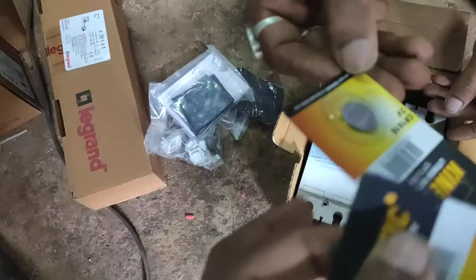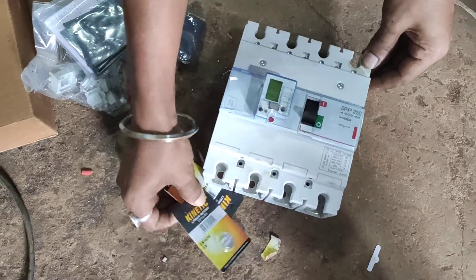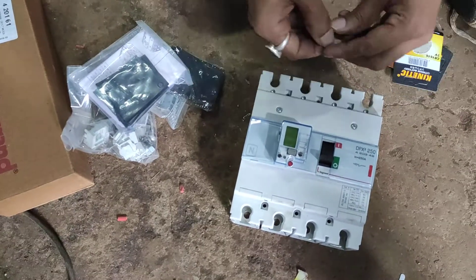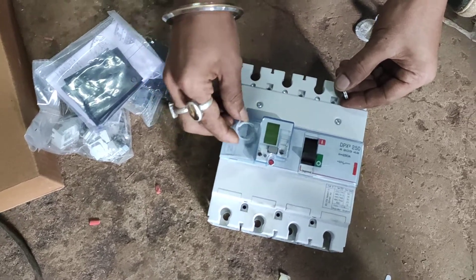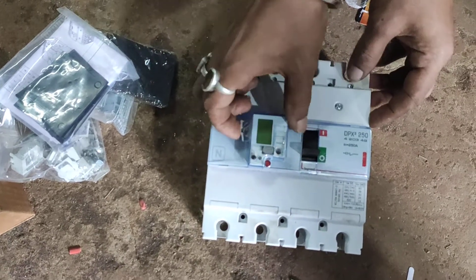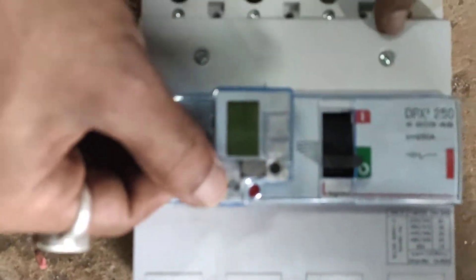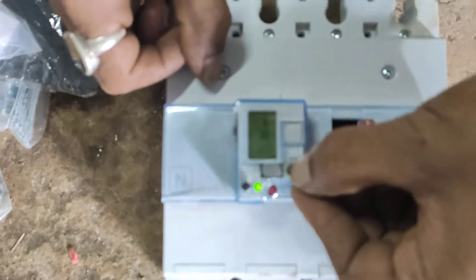Here you can see the batteries. The main feature of this MCCB is that you can also operate it in SCADA. The battery helps you regulate it in different modes of load. It's 250 ampere at full load, but if the load is lower you can adjust it to 150 or 200 ampere. This is the battery slot. You can see my mate putting the battery inside the MCCB — it's done. It's switched on: you can see 250 ampere, and you can operate it through the knob. The light blinks on the lower side, which means it's working.